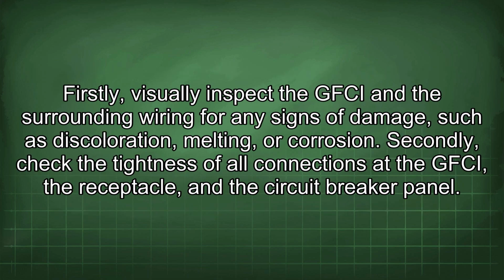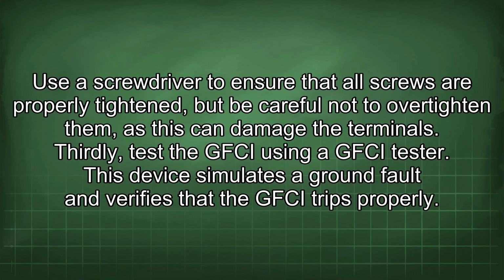Firstly, visually inspect the GFCI and the surrounding wiring for any signs of damage, such as discoloration, melting, or corrosion. Secondly, check the tightness of all connections at the GFCI, the receptacle, and the circuit breaker panel. Use a screwdriver to ensure that all screws are properly tightened, but be careful not to over-tighten them, as this can damage the terminals. Thirdly, test the GFCI using a GFCI tester.